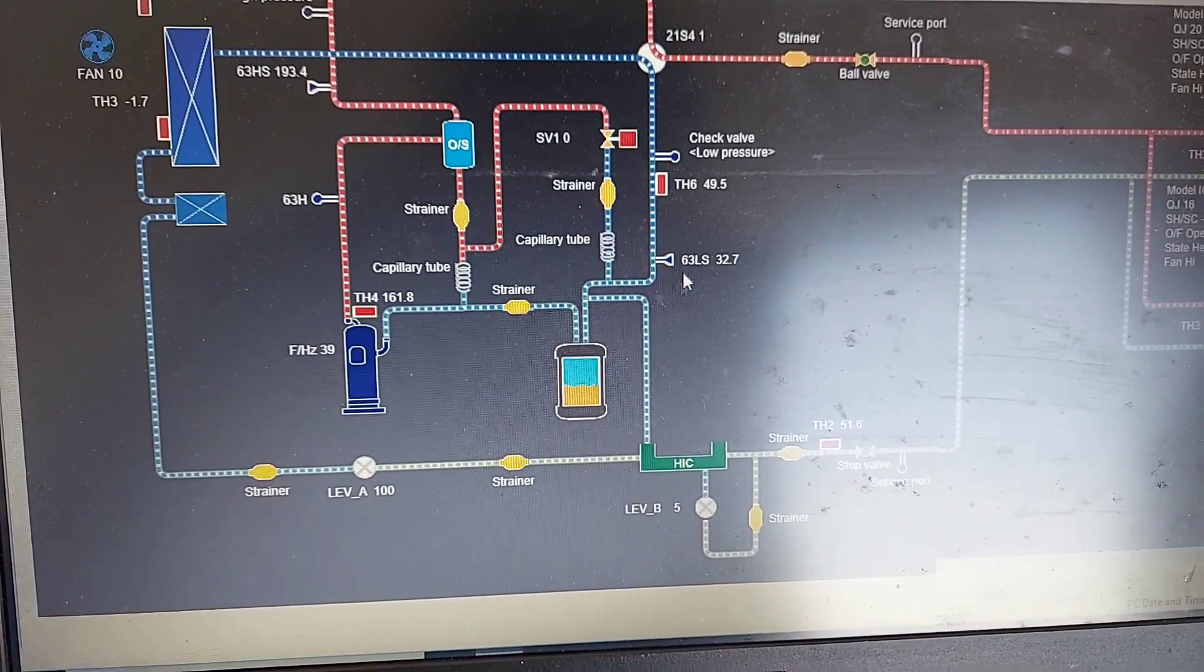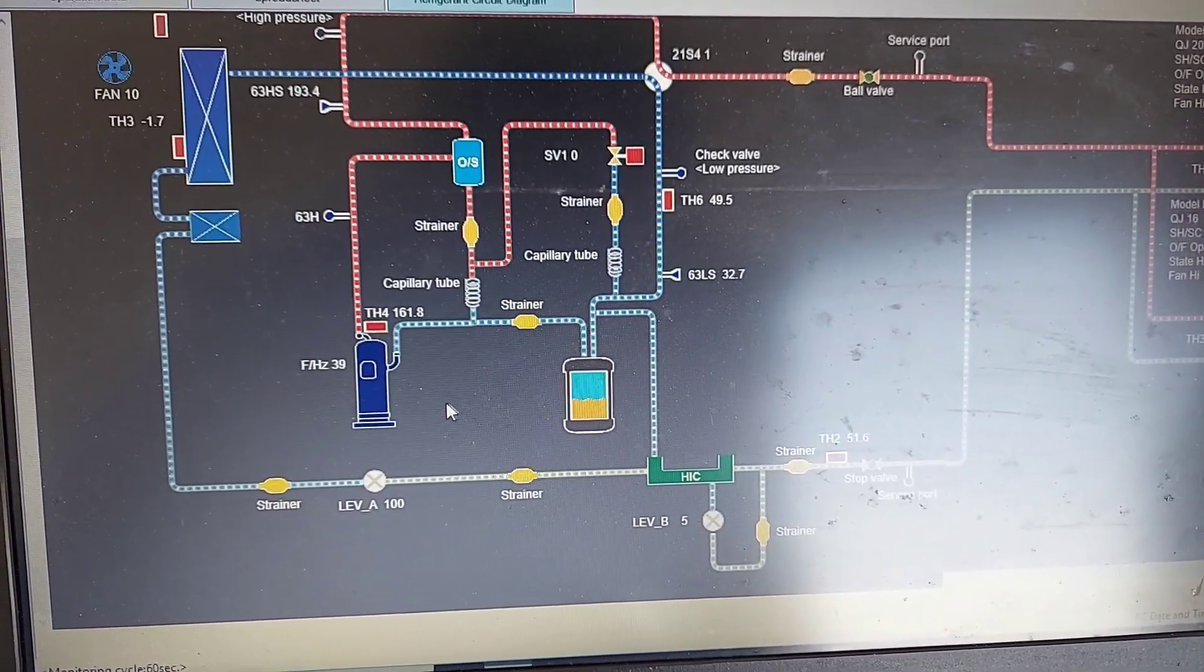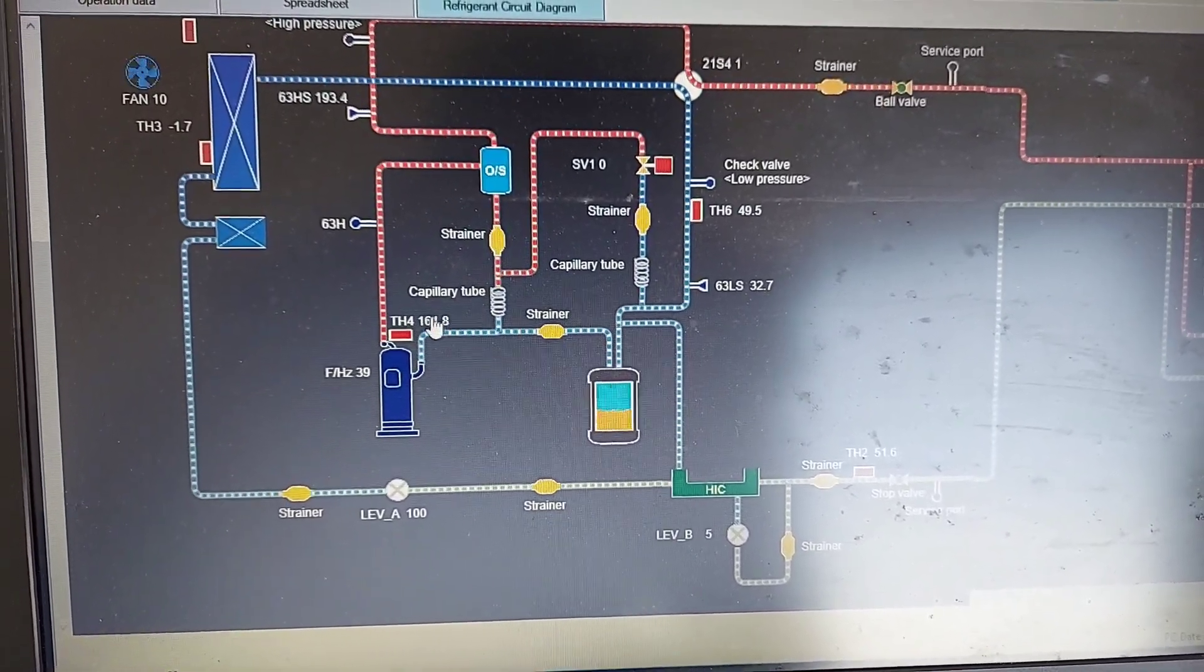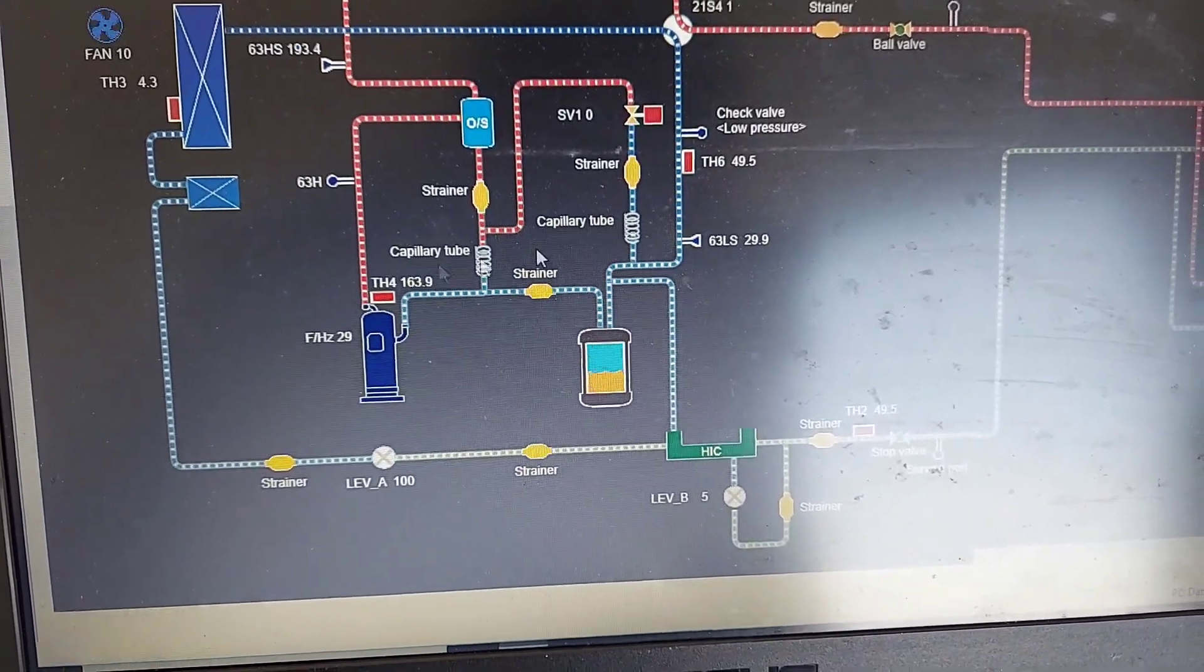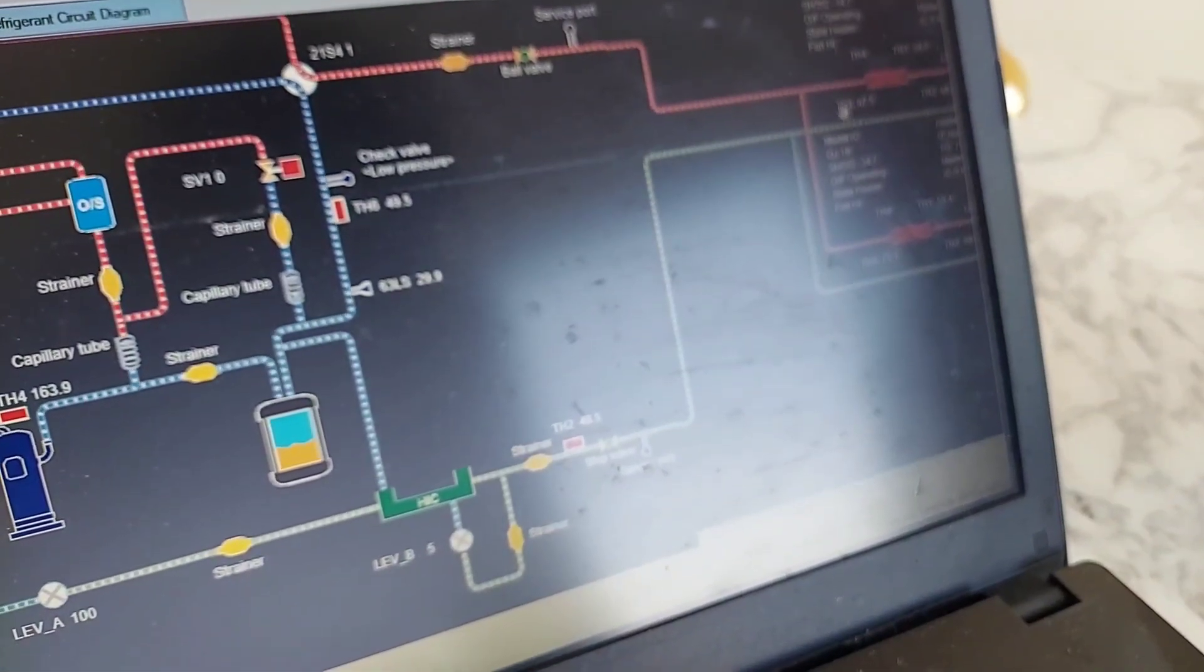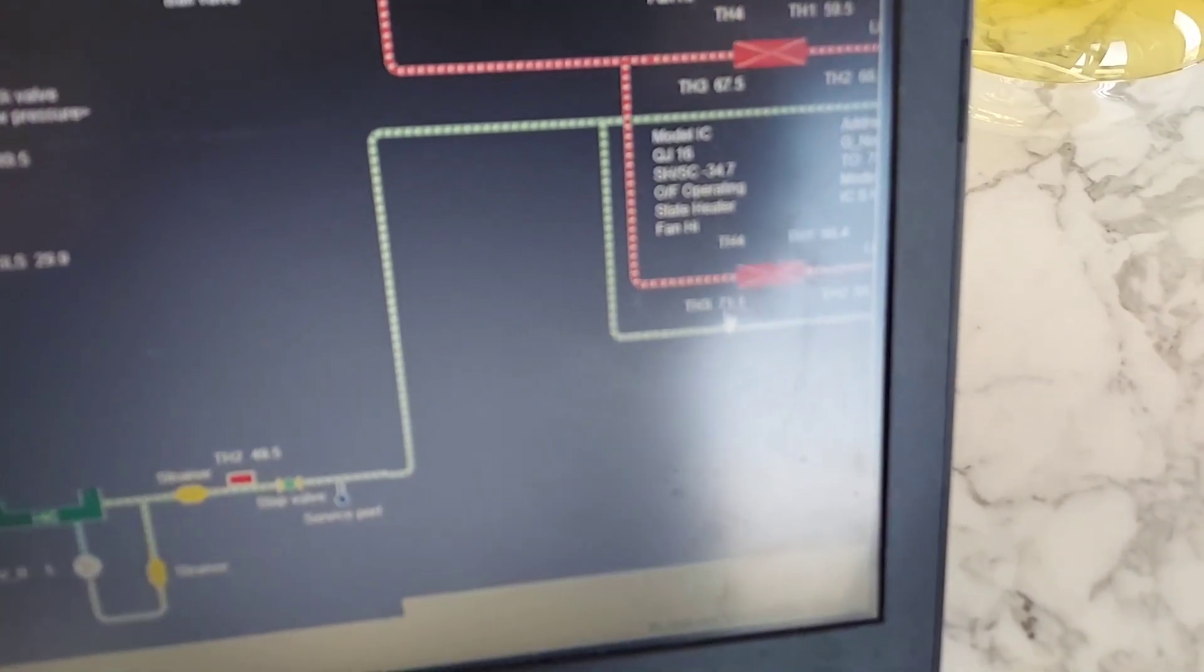From experience it's going to be good. Compressor 39 hertz and this is going to go and get hotter and hotter until it goes into a preliminary, then it's going to go into an actual fault. See, I'm still at 67 here, I've not changed, I'm not, I've barely moved on this one. This one is at 71 right, so huge difference there guys.